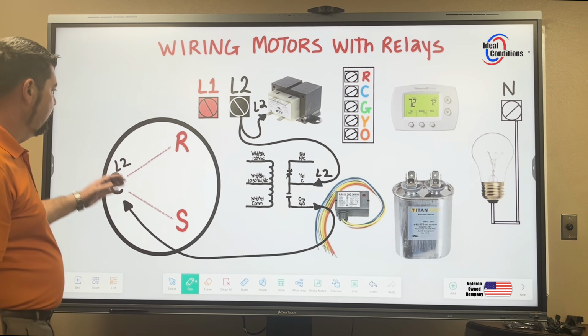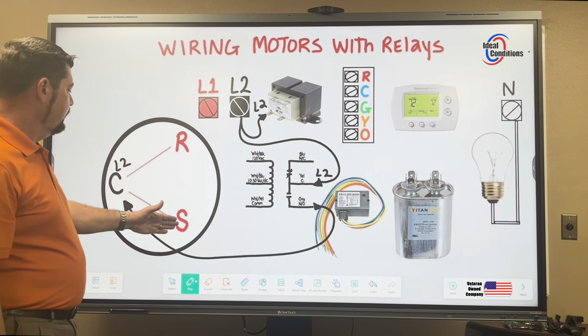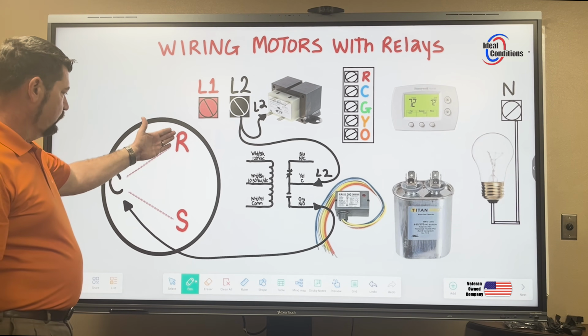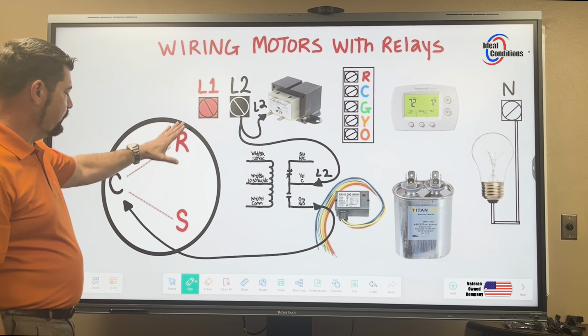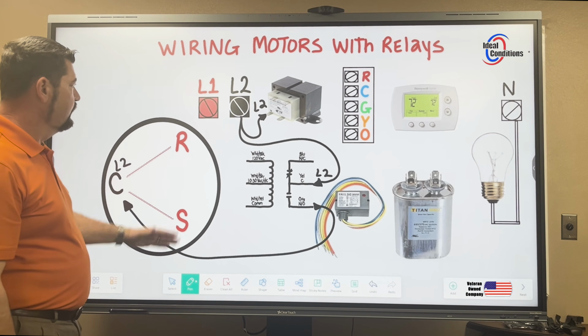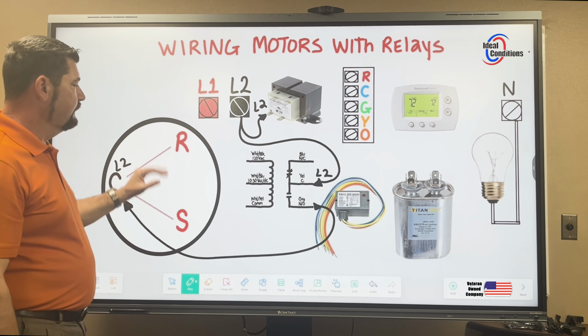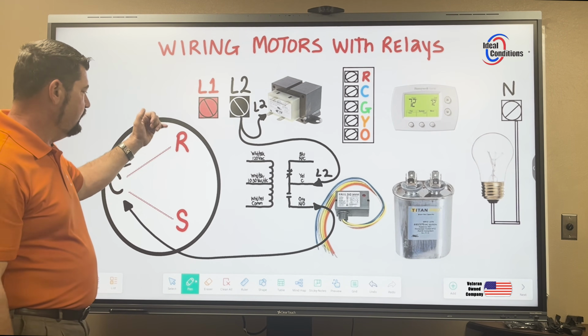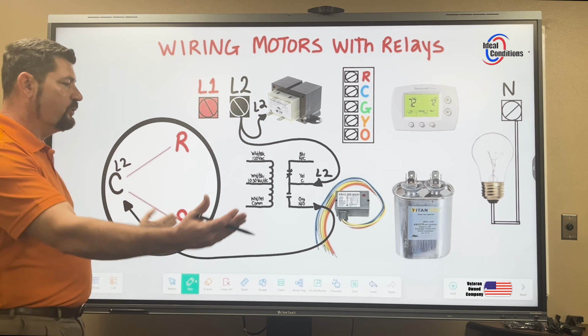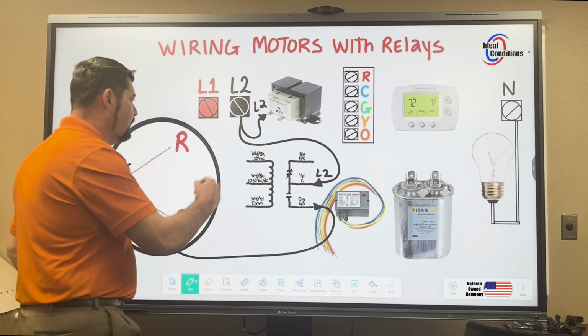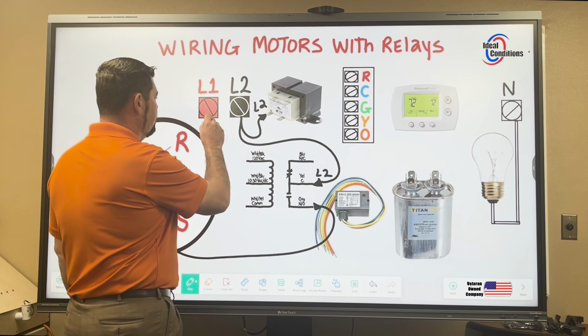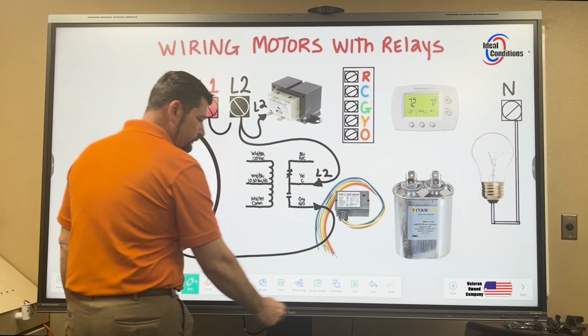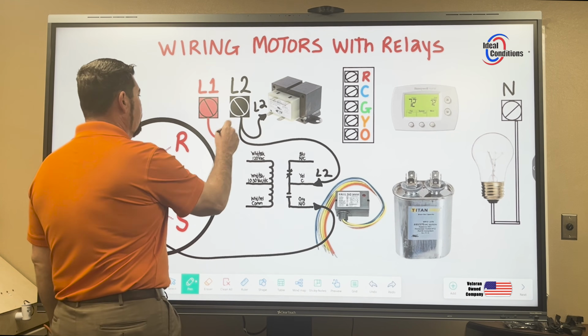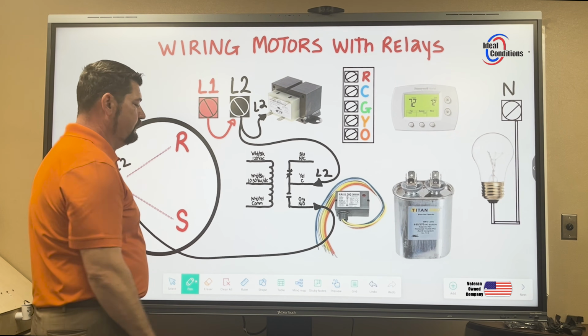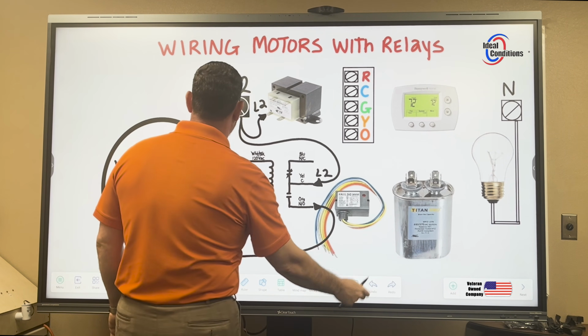Check. Now if you notice, R and S stand for run and start, and they're both the same color, red, as well as L1. It doesn't have to be that. It's just to show you that these will be on this same leg of power. So I, again, don't cross paths. And what I mean by cross path, I'm talking about L1 to L2. That would not be good. So we're trying not to cross paths at all.